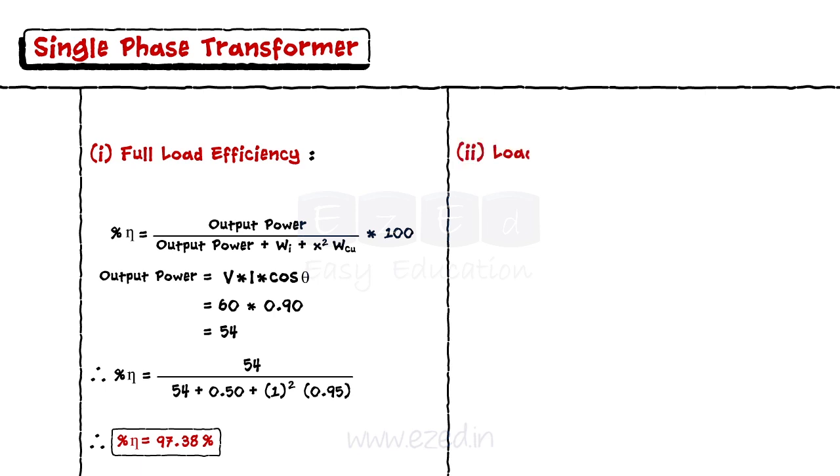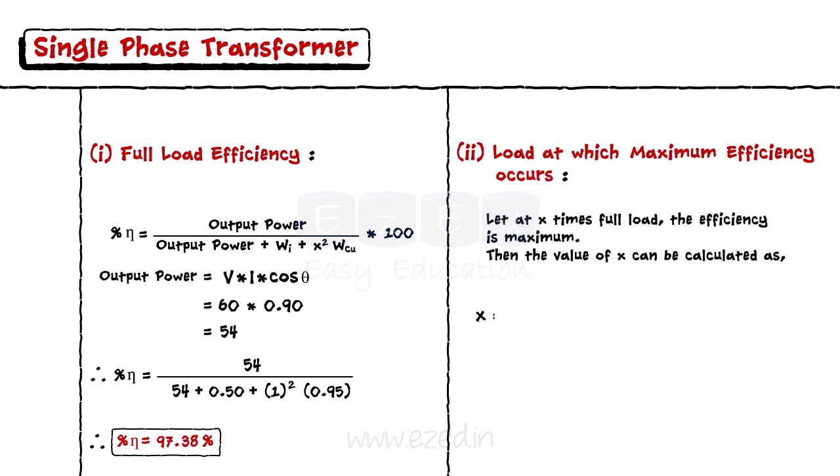To calculate the load at which we get the maximum efficiency, we use formula x equals square root of iron loss upon full load copper loss equals 0.5263. Thus, at 52.63% of full load, we achieve maximum efficiency.